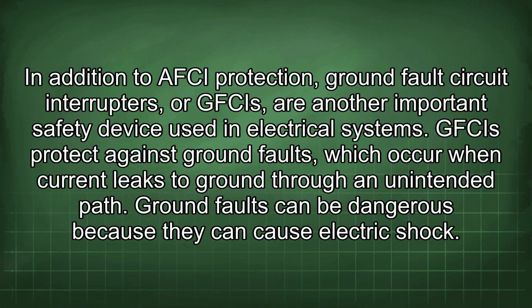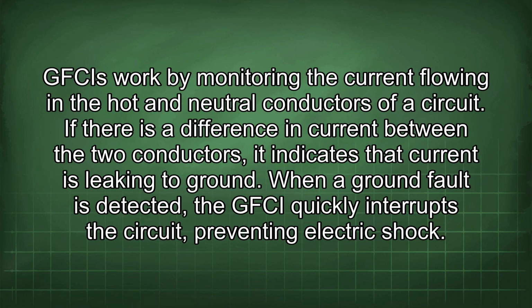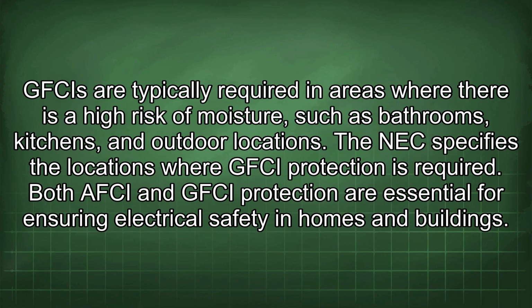In addition to AFCI protection, ground fault circuit interrupters, or GFCIs, are another important safety device used in electrical systems. GFCIs protect against ground faults, which occur when current leaks to ground through an unintended path. Ground faults can be dangerous because they can cause electric shock. GFCIs work by monitoring the current flowing in the hot and neutral conductors of a circuit. If there is a difference in current between the two conductors, it indicates that current is leaking to ground. When a ground fault is detected, the GFCI quickly interrupts the circuit, preventing electric shock. GFCIs are typically required in areas where there is a high risk of moisture, such as bathrooms, kitchens, and outdoor locations. The NEC specifies the locations where GFCI protection is required.